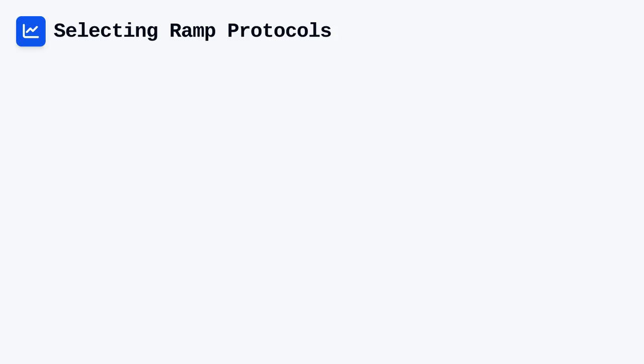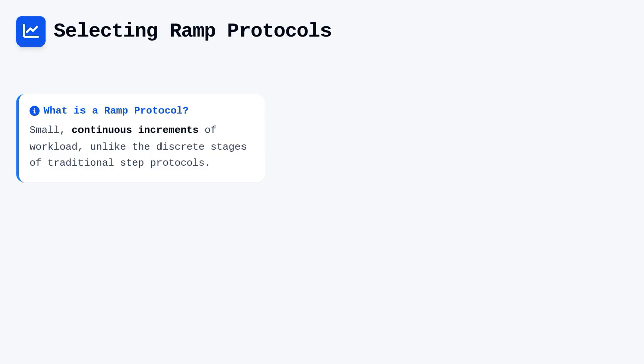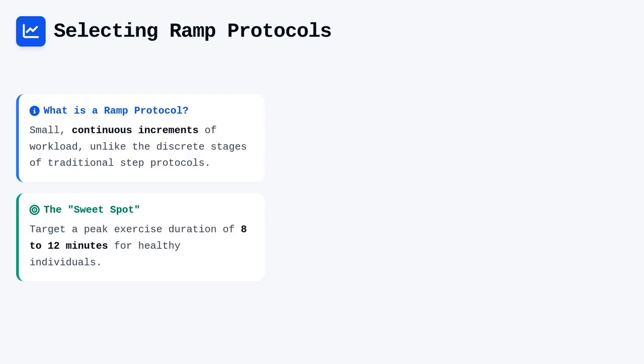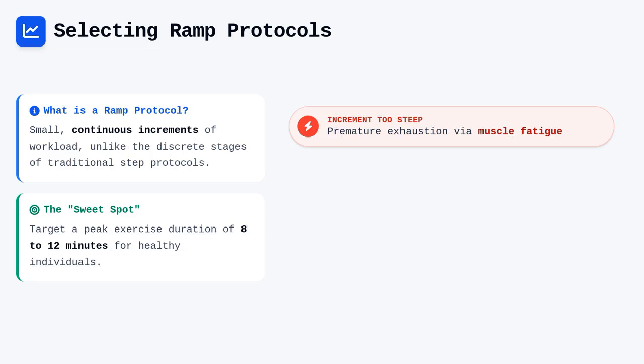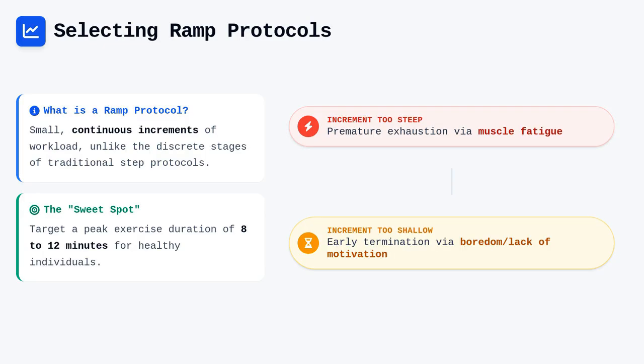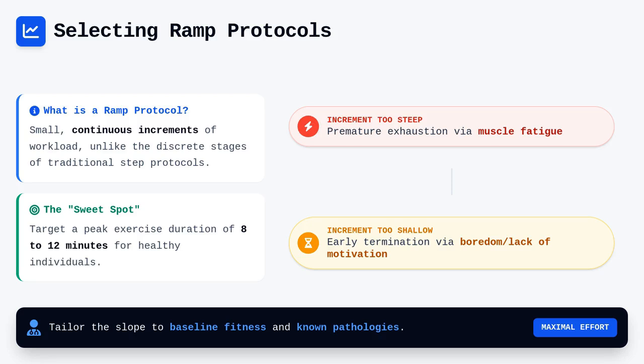Selecting the appropriate ramp protocol is a strategic decision that balances patient tolerance with the need to reach a true maximal effort within a reasonable time frame. A ramp protocol increases workload in small, continuous increments rather than the larger, discrete stages found in traditional step protocols. For the average healthy individual, a work rate increment that leads to a peak exercise duration of approximately 8 to 12 minutes is ideal. If the increment is too steep, the patient will reach exhaustion prematurely due to muscle fatigue rather than cardiovascular limitation. Conversely, an increment that is too shallow prolongs the procedure unnecessarily, increasing the likelihood of early termination due to boredom or lack of patient motivation. Always consider the patient's baseline fitness level and known pathologies when choosing the ramp slope to obtain the most representative aerobic capacity measurement.